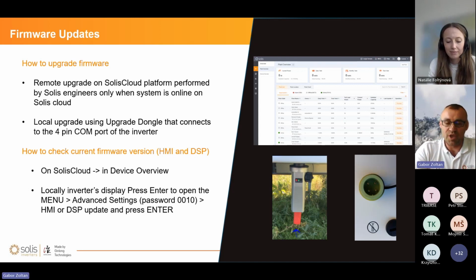If you want to check the firmware state, what firmware you have on the inverter, you can check it via Solis Cloud. Go to the device overview and you can find the firmware version, or on the display, not on the new one, because the new S6 has no LCD screen, the older models or the grid ties. Go to the menu, the advanced settings, and you can check the HMI or the DSP update and check the state.